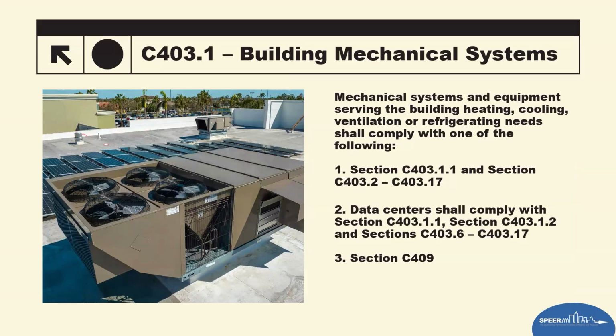code. Most buildings are going to follow C403.1 and 403.2 through 403.17, which outline all the efficiencies, the controls, the ventilation, and the performance of the equipment. But they've now started to address data centers in a different category. Data centers have slightly different paths due to their unique cooling demands. They have different sections in there for data centers. And then section 409 can be used for energy monitoring and advanced efficiency requirements as well. The goal here is for this section to ensure that commercial HVAC and refrigeration systems operate efficiently, are properly controlled, and meet minimum performance standards aligned with today's technology and energy expectations.